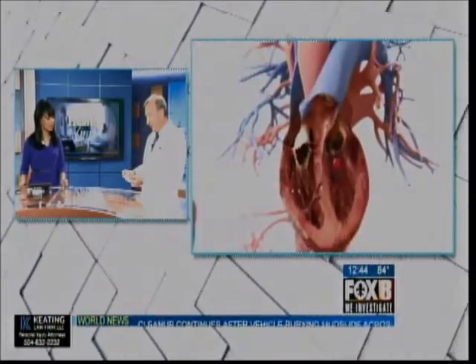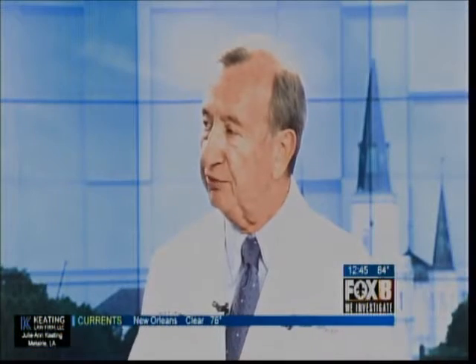So you brought an example of it. This thing is so tiny. How does this work? This just peels off, and it sits like this on the skin. And it actually stays on very nicely for 14 days. So it's like a little patch — it's called a Zio Patch, exactly. What are the advantages for your patients locally? The advantage is patients prefer this because it's so much easier. They don't have several electrodes to deal with. If they feel like they're having palpitations, they can just press the top here and it'll mark the reading.